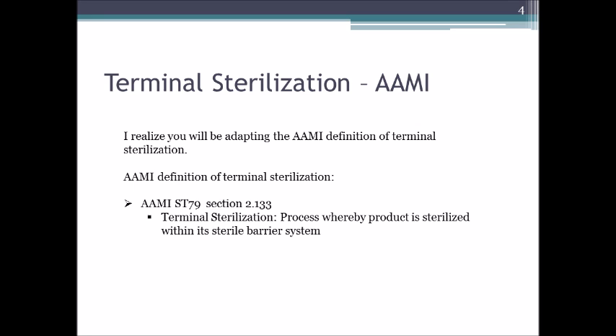It's a process whereby product is sterilized within its sterile barrier system. That's important to state, because as we start to understand what this technology does, a lot of times people get confused with terminal sterilization versus what the dry time does. The dry time literally doesn't have anything to do with the actual sterilization of the device, but sometimes people intermingle the two, and we wanted to define that here.